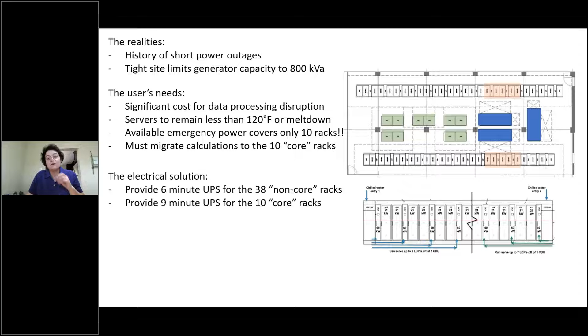Last but not least, the mechanical problem was: as soon as we lose power, we lose everything. The chiller plant was too large to run on that emergency generator, and on our air-cooled chiller, it took 6 minutes to get up to full capacity. So what are we going to do in that 6 minutes?